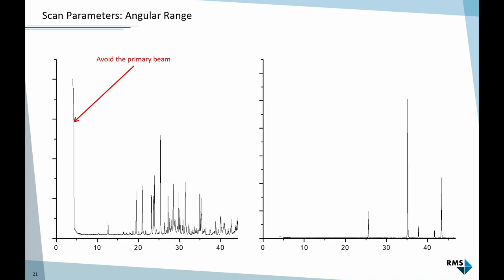On the other hand, here's an example - I think it's corundum, a reference sample. I started at four degrees, my standard starting angle. It took me half the time to measure this sample just to measure background. There's no information. If I know that, if I have an idea of my composition, I can avoid that. I could speed up the measurement by factor two, just by skipping and starting maybe somewhere between 20 and 25. There's no need to measure empty background - it doesn't contain useful information.